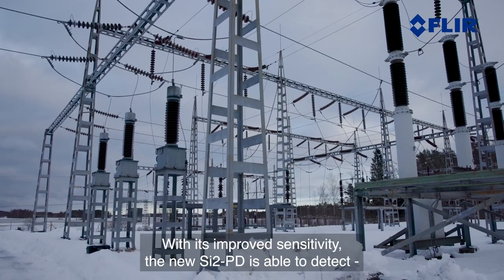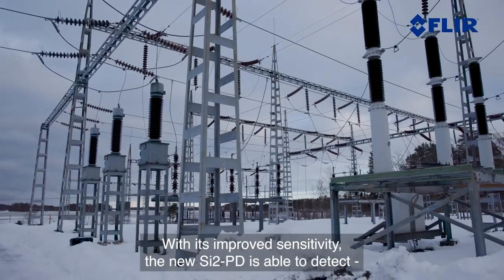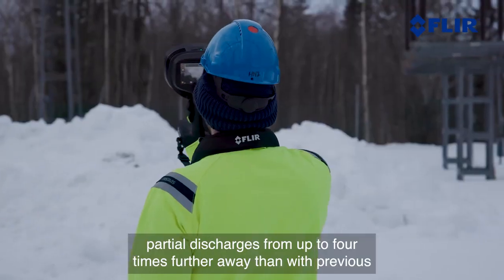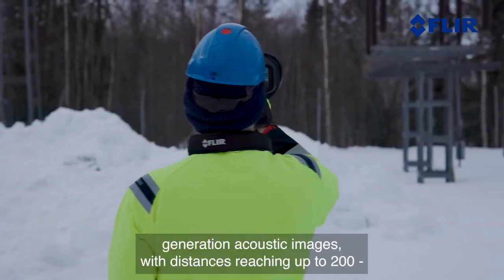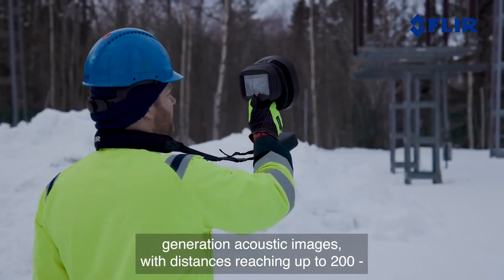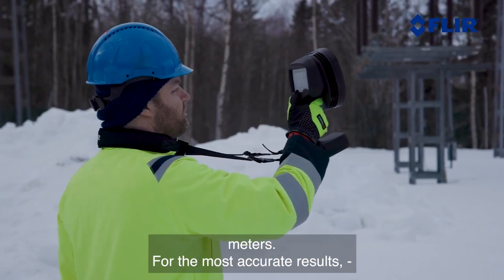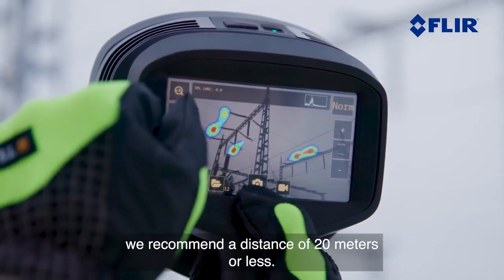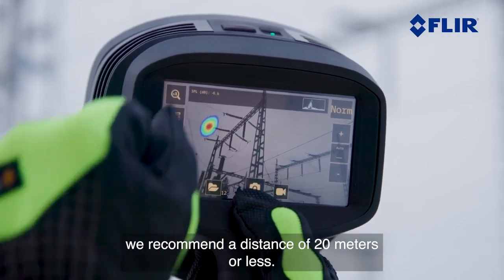With its improved sensitivity, the new Si2PD is able to detect partial discharges from up to 4 times further away than with previous generation acoustic imagers, with distances reaching up to 200 meters. For the most accurate results, we recommend a distance of 20 meters or less.